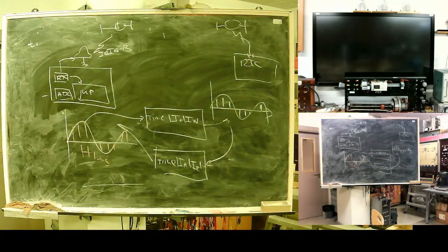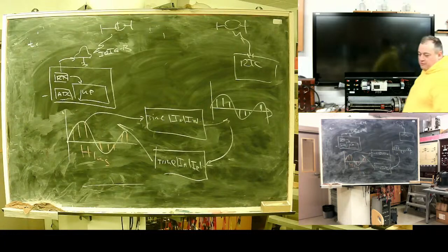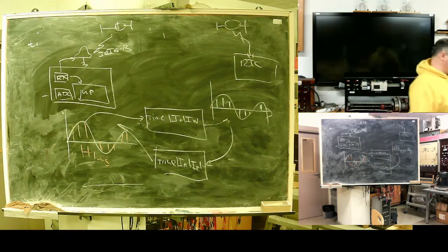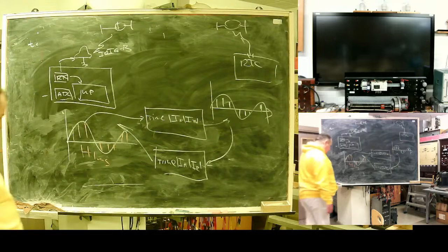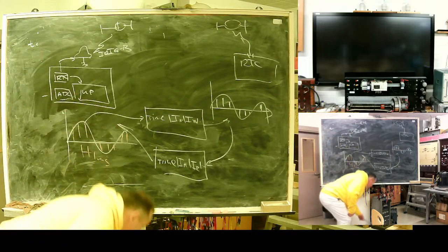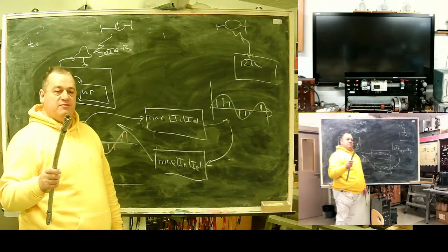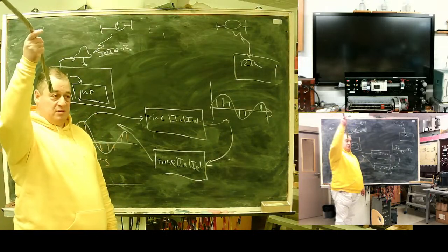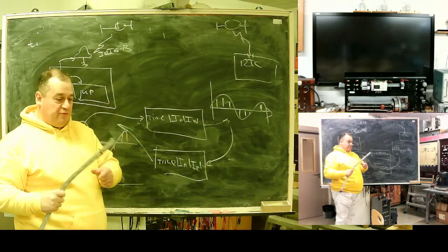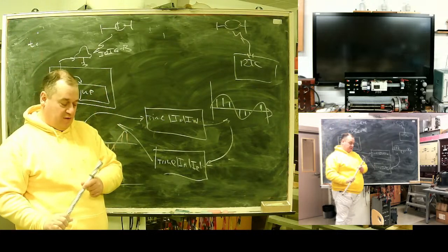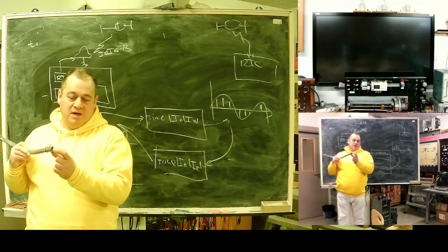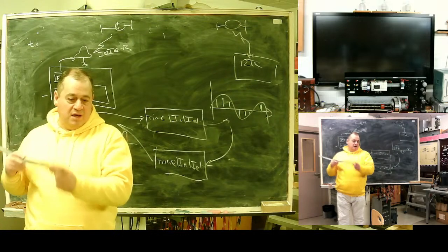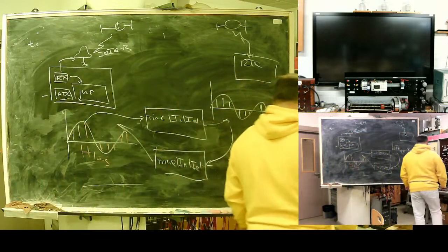Bad thing, because of money saving, often this data communication channel, fiber optics, goes the same road as our line. For a more, how to say, luxurious design, it is OPGW, so-called. It's a protective cable on the top of the towers. Inside, it's a small plastic pipe, and here should be fiber optics.